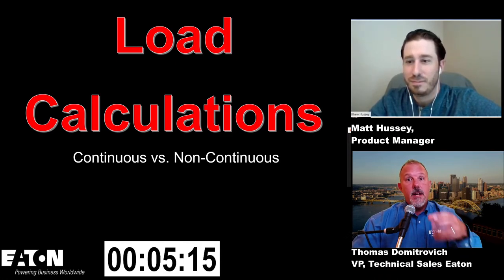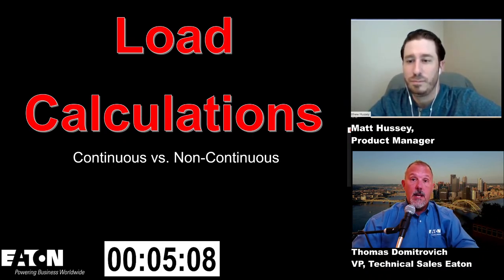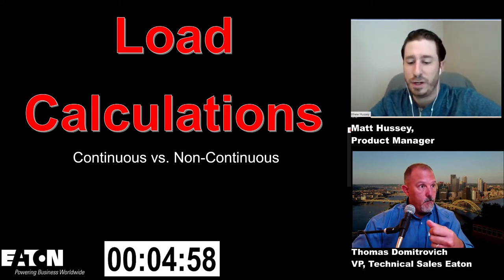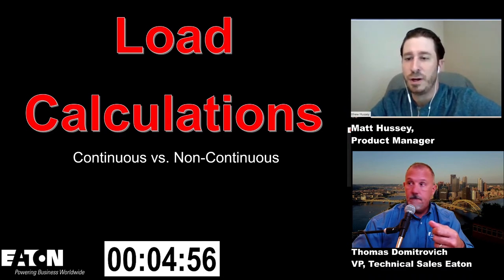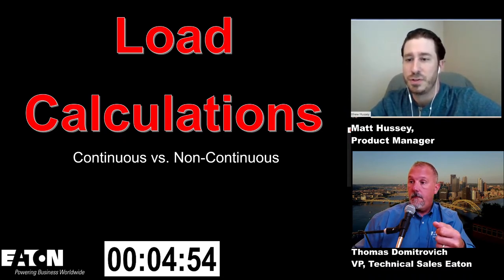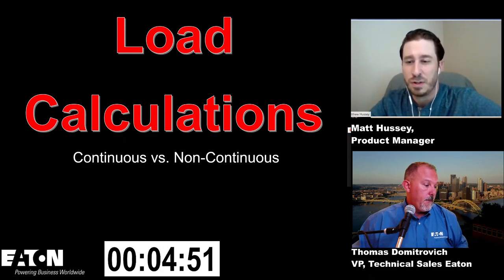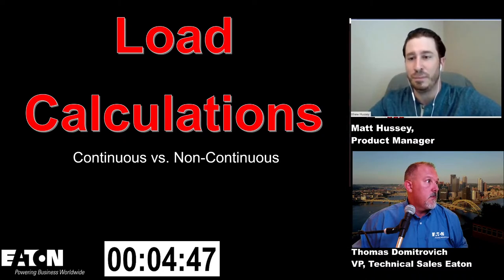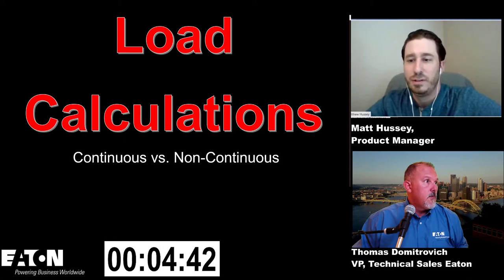It's the amount of copper that I'm putting on the lugs of that overcurrent protective device, which doesn't match what's in the standard, UL 489, which means that I'm relying on that load conductor to take some of the heat out of the circuit breaker, right? Yeah, you don't want that circuit breaker to exceed a temperature rise or get into a situation such as thermal runaway, where you get nuisance operation and things like that. All that's meant to keep things in balance. The moment something changes off that, we have to correct for it.